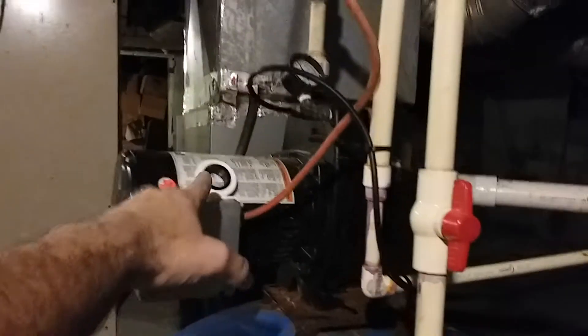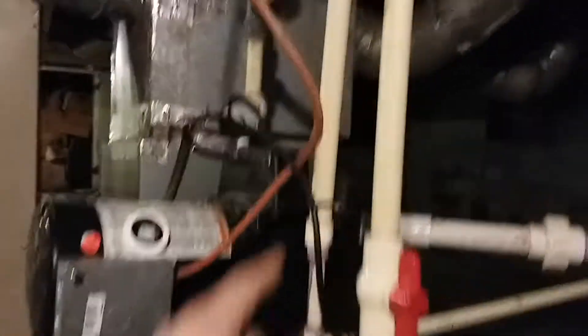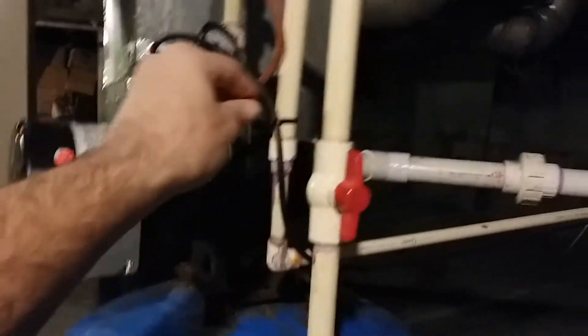Up here is the pressure pump — I call this pump A. I don't have a pump B yet, but the system is already programmed for it. I've tapped off the pressure line and it comes up here to a Yokogawa pressure transmitter. This thing outputs 4 to 20 milliamps — 4mA at 0 psi and 20mA at 169 psi.